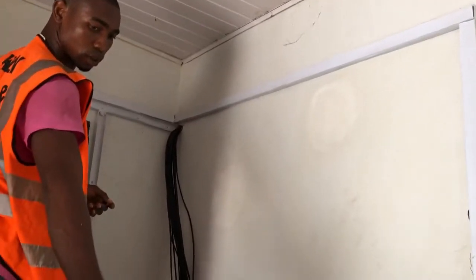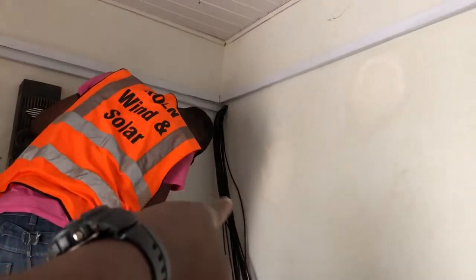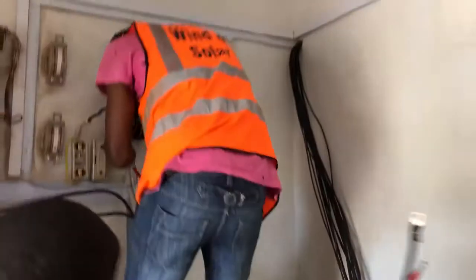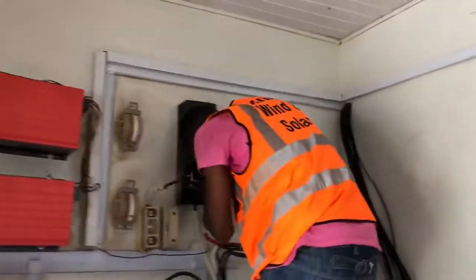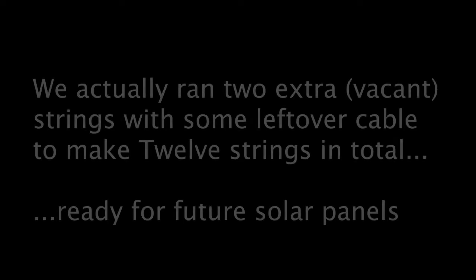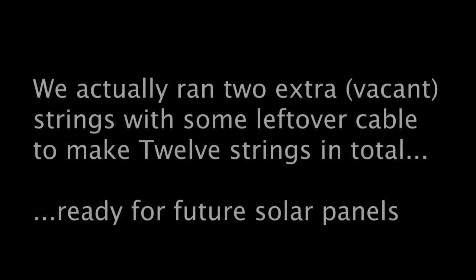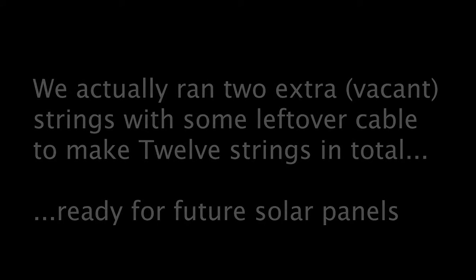Okay. We've set solar recharge cables down that way. Proper 4mm solar DC cables from the roof in 10 strings, not one string, 10 strings. Good. Although actually we did run 2 extra strings to make it a total of 12, so for future expansion, buying extra panels, we wouldn't have to run any wiring.